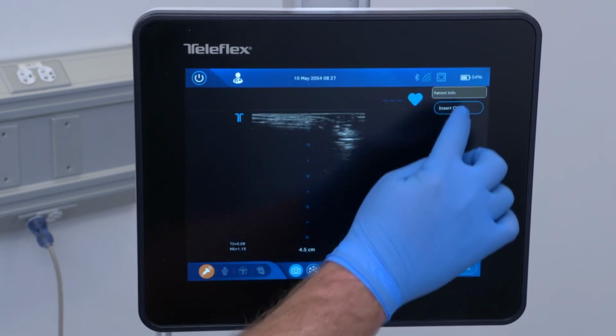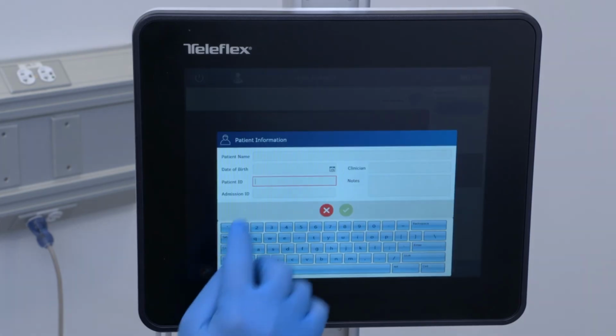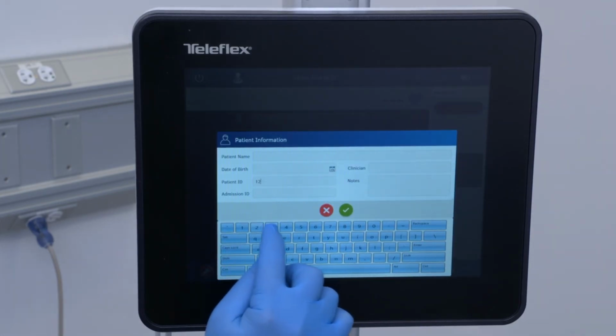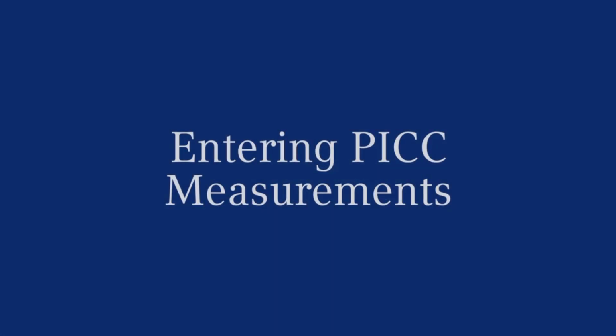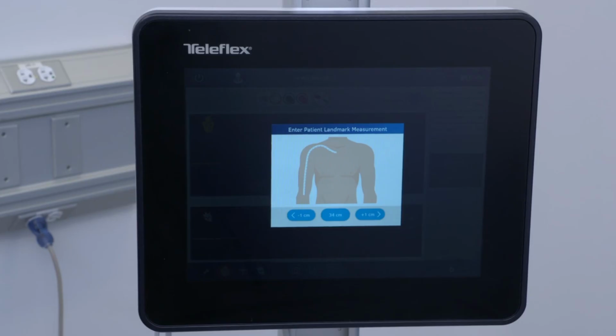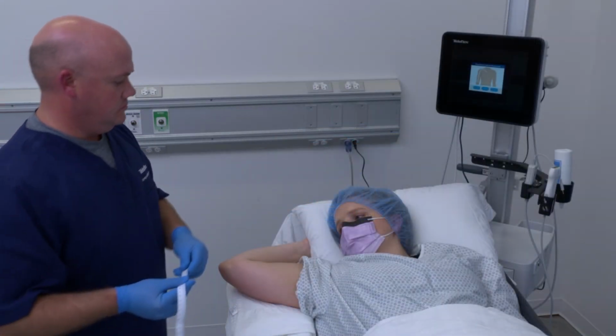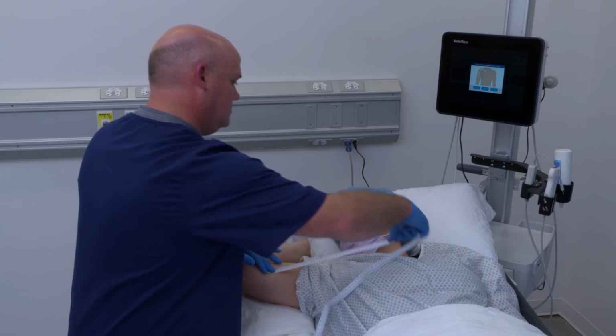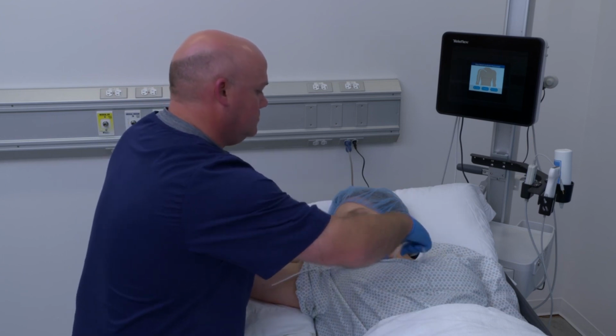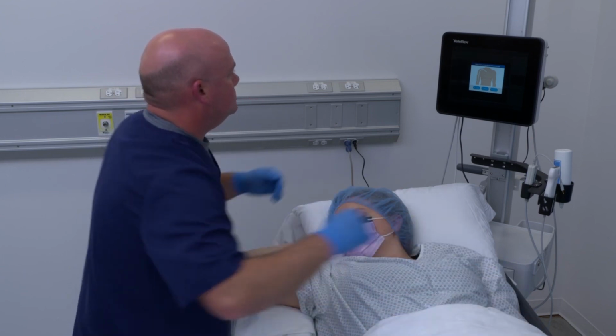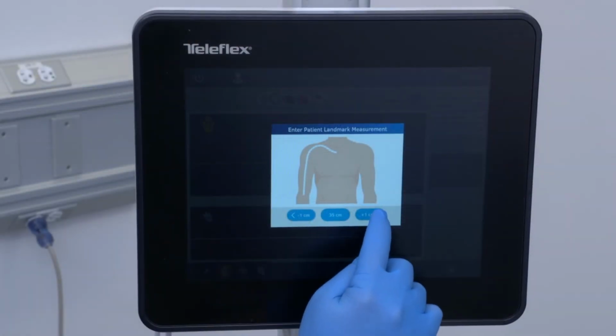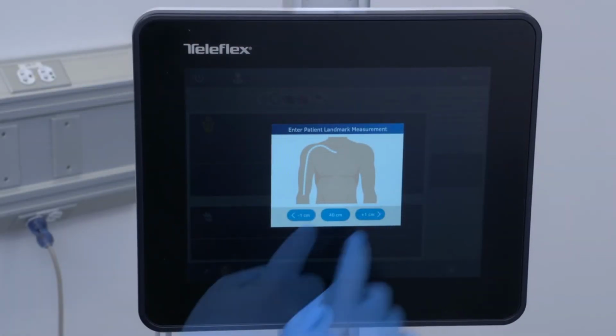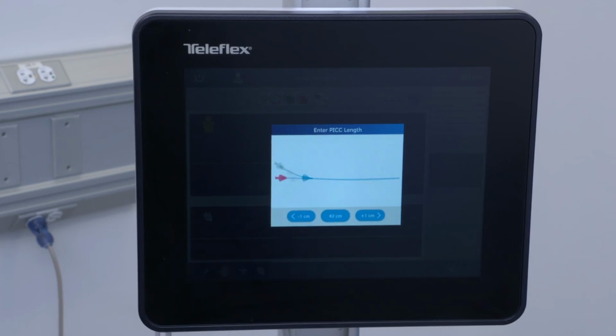When the ultrasound vessel assessment is complete, select Insert CVAD. Enter a unique patient ID and select the green check mark. Select PICC. When PICC is chosen as the catheter type, measurements must be entered by the clinician. Use the arrows and selection icons to enter the patient landmark measurement. From the Enter PICC length screen, use the arrows and selection icons to select the PICC length.